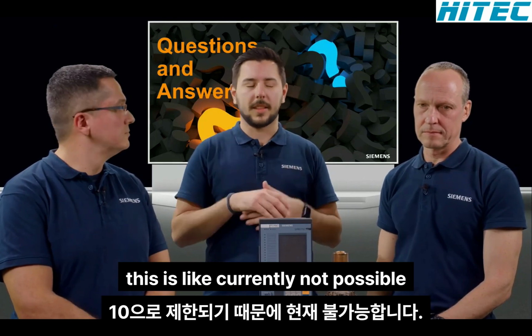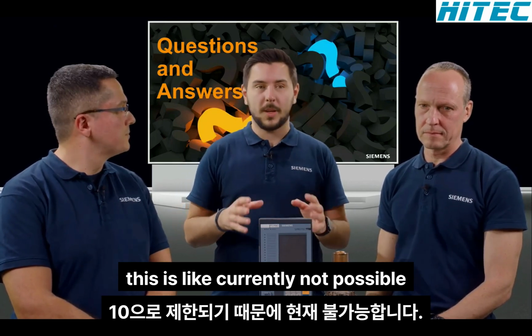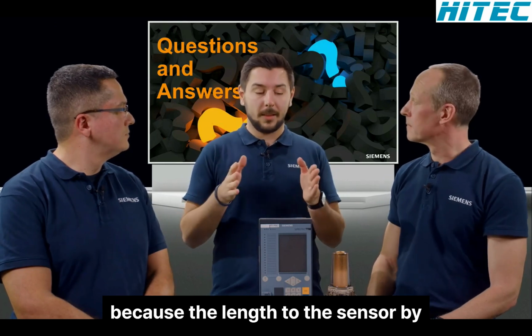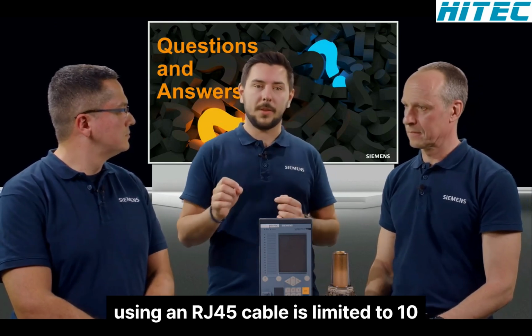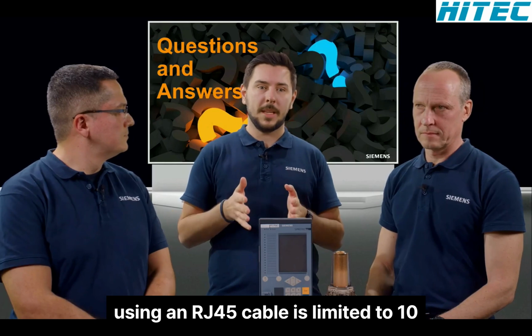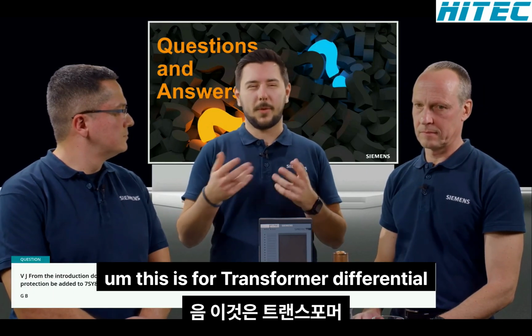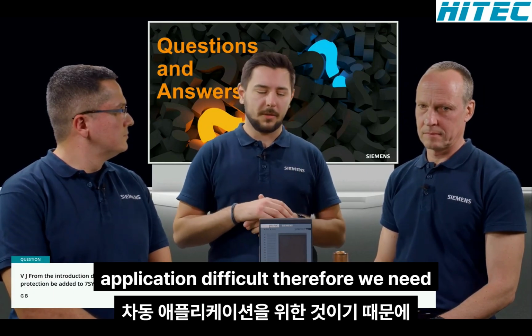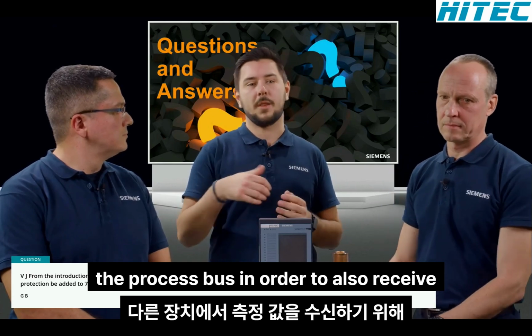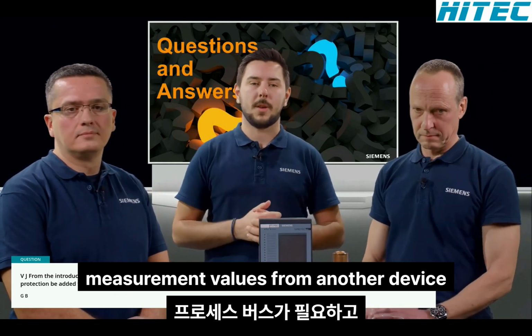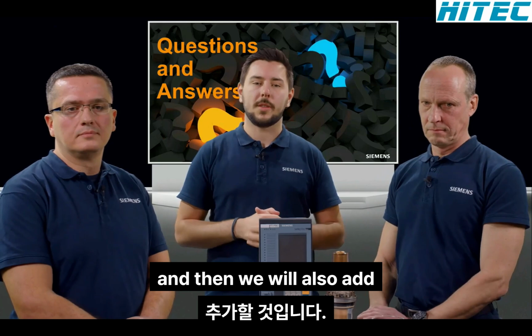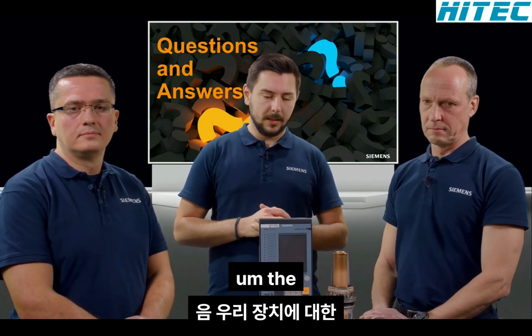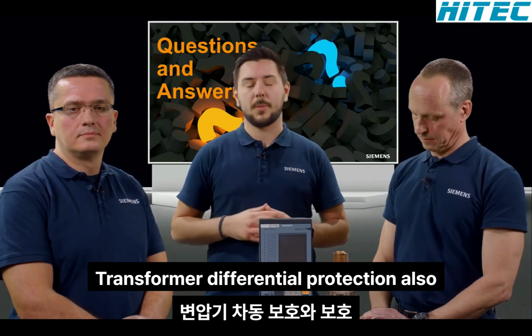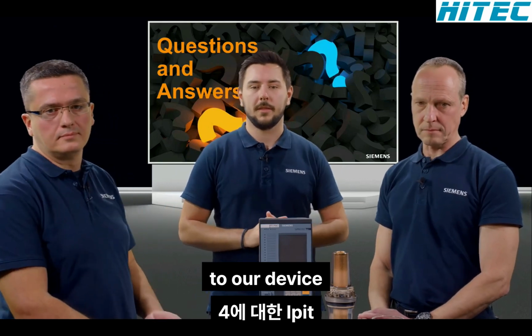This is currently not possible because the length to the sensor using an RJ45 cable is limited to 10 meters. This is difficult for a transformer differential application. Therefore, we need the process bus in order to also receive measurement values from another device. And then we will also add the transformer differential protection to our device.